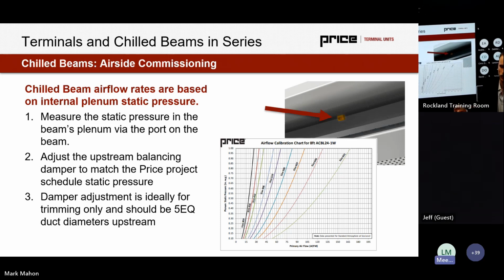Yes, but we can take each beam and duct them back to a single terminal. So we could have 4 beams to a terminal. And so that would allow for measurement and control of all of the beams serving the same zone with one terminal. Ideally, what we would do is have one VAV terminal per zone. With really large zones, that might not be possible. For instance, a zone that would require 650 CFM of ventilation, like a really large zone, we would probably split that zone in two and have 2 terminals serving however many endpoint beams we need to properly mix and condition the space.